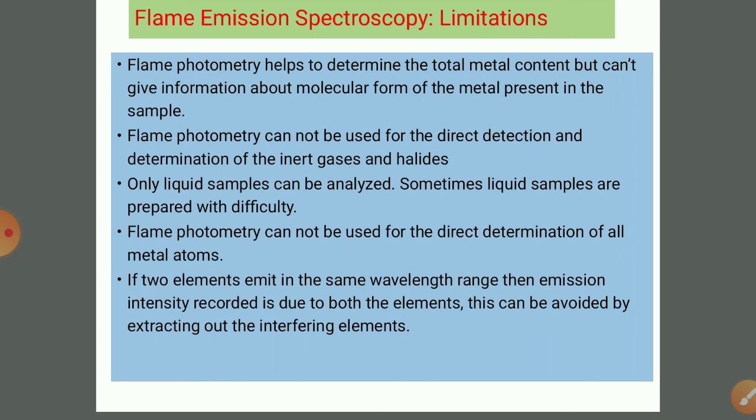The next limitation is that in flame emission spectroscopy only liquid samples are analyzed, but sometimes liquid samples are prepared with great difficulty. Flame photometry cannot be used for the direct determination of all metal atoms. So this is also one of the major limitations of flame emission spectroscopy.